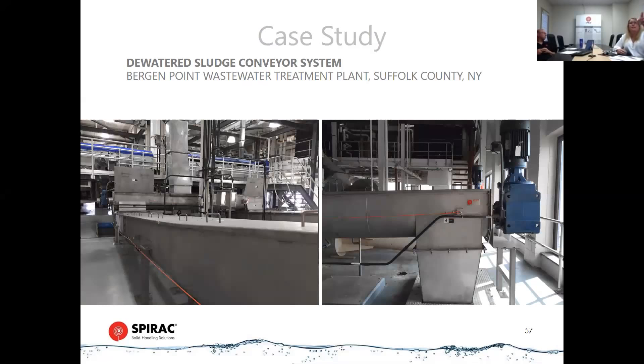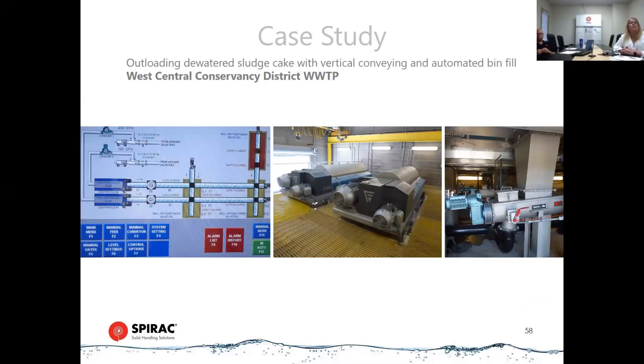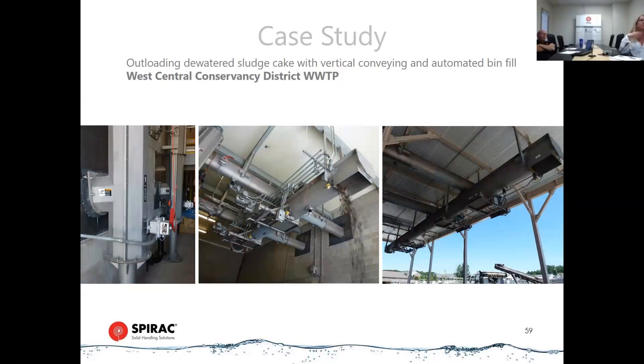You can see the discharge on the last conveyor on the right. One more case study is West Central in Avon. They have some centrifuges that discharge to short inclines, go up to verticals, and there are a lot of trucks. What's cool about this installation is it's fully automated — ultrasonic level sensors, everything talking together, so there's not someone sitting there saying what to do. The sensor says, okay, outlet number one is full — shut my gate and move on to outlet number two, or change directions to go to the other outlet. It's fully automated with very little operator interface.